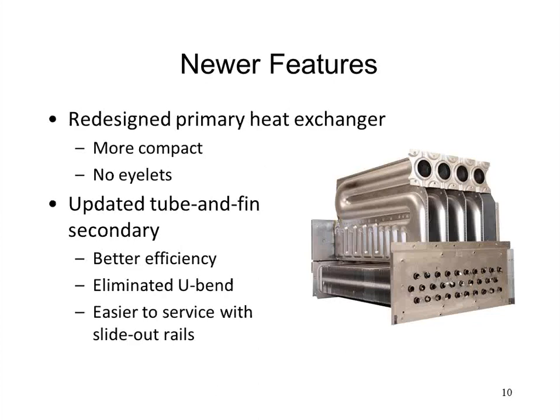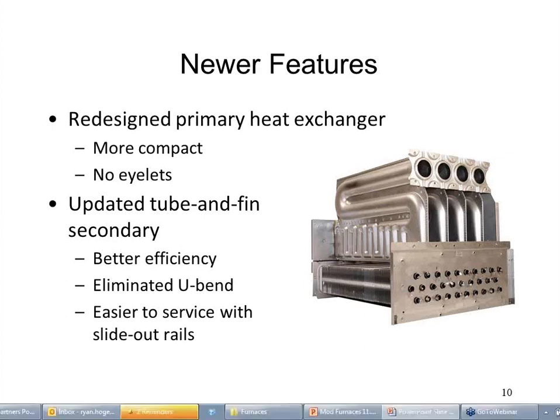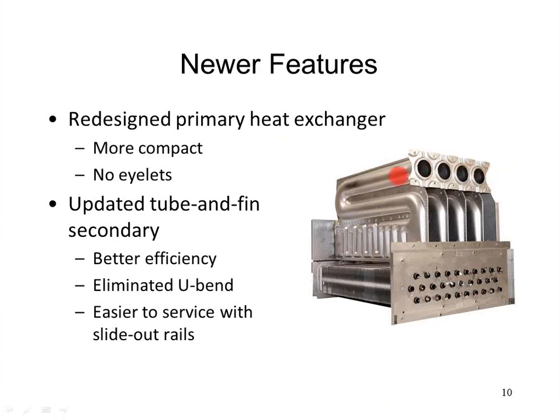This gives you a better view of what the heat exchanger looks like on the inside. Like I had said, let's see if we can get this back over here. This is a 4-cell heat exchanger in this particular model that we're showing you here. All your burners are up top here. Combustion's happening in this point. All of our flue gases are coming through, wrapping around the back, passing through again. And it looks like they zigzag up and down, but they really do move kind of straight through here. The zigzagging look there is to get us more surface area to get more heat transfer and hence more efficiency.